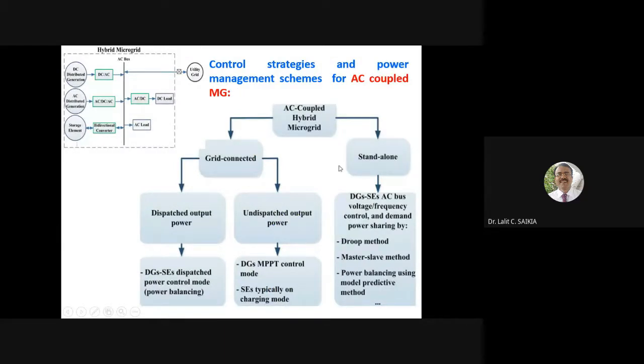Now, what is the control strategy and power management scheme for AC coupled microgrid? We have shown that this is an AC coupled microgrid - all the DGs and energy storage elements are connected to a common AC bus via power electronics converters, and the utility grid is connected from this AC bus. AC load can be directly supplied from the AC bus if the voltage rating matches the load voltage, and if a DC load is there, that can be supplied from here as well.